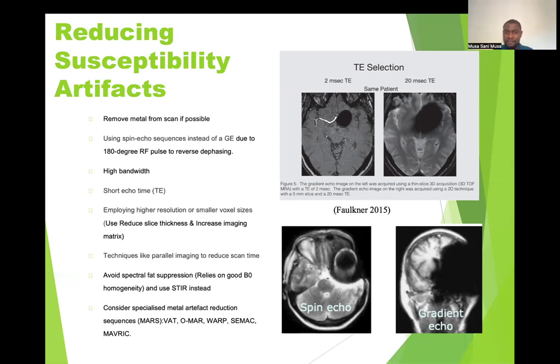If you use a gradient echo with a 20 millisecond echo time, it's a waste of time, because the image is not going to be diagnostic. So instead, there are some 3D sequences which have a very short TE of 2 milliseconds. They give you a good image. Use spin echo sequences, it could be fast spin echo or turbo spin echo, as opposed to gradient echo. Like I said, gradient echo is very, very susceptible to metal artifact.